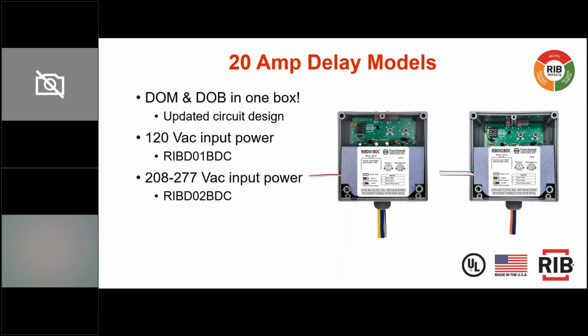We also have those 20 amp delay models that were mentioned earlier. Again, delay on make and delay on break. That's what the DOM and DOB stand for. Delay on make, delay on break. And it comes in one box. Before, it was two different model names you had to look for and choose. Now it's the same thing in one box. And they come in two flavors, 120 volt AC input or 208 to 277 volt AC input power. And again, those dry contact inputs, it's the low voltage 24 volts that helps to control that timing element.